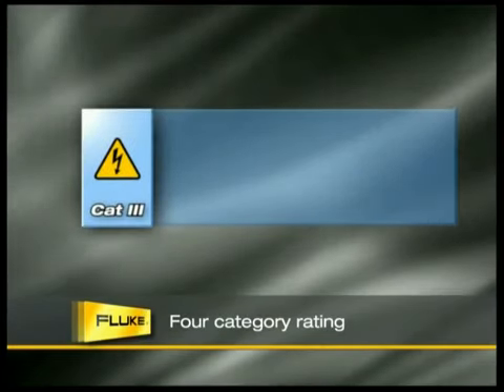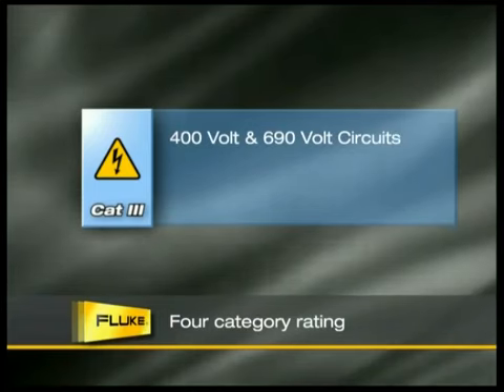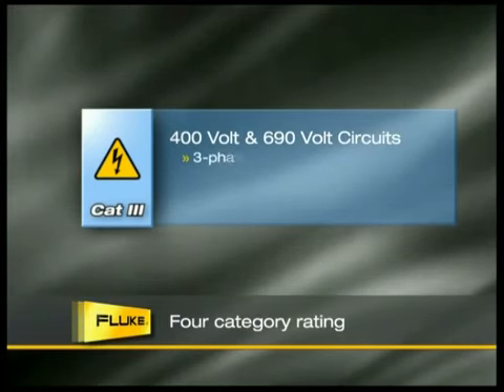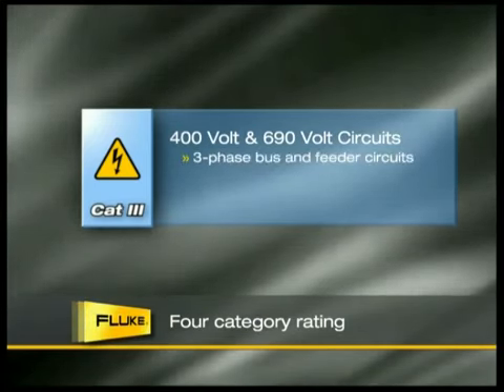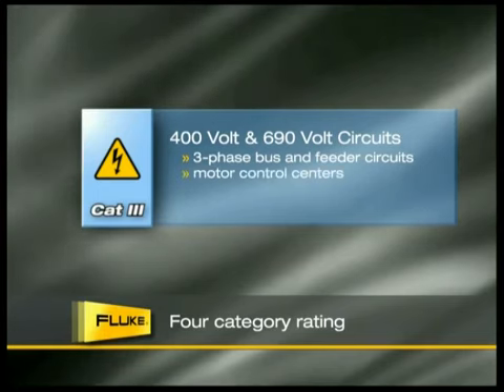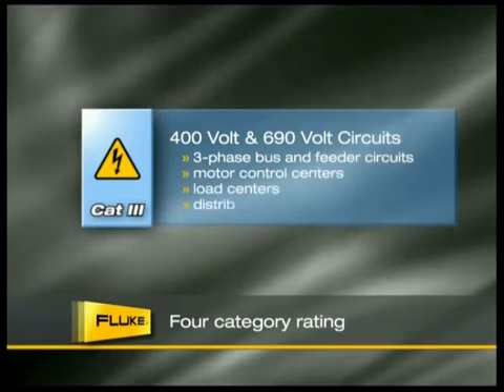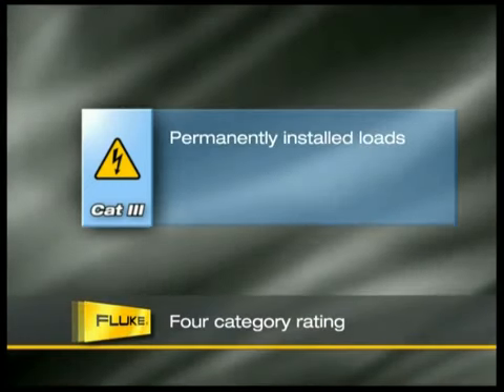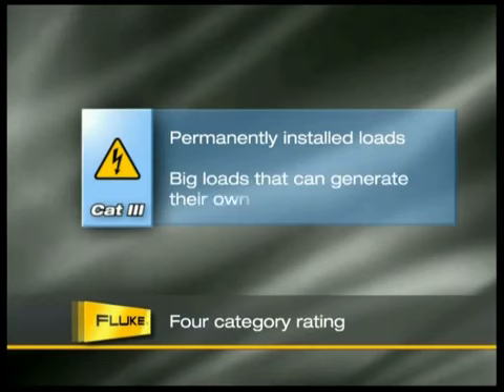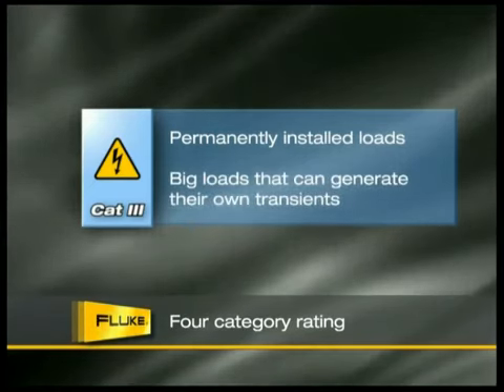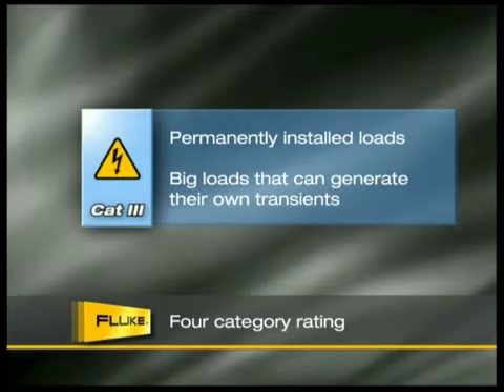Cat 3 covers distribution-level wiring. This includes 400 or 690-volt circuits, such as three-phase bus and feeder circuits, motor control centers, load centers, and distribution panels. Permanently installed loads are also Cat 3. Cat 3 also includes large loads that can generate their own transients and are now more common than many people realize.